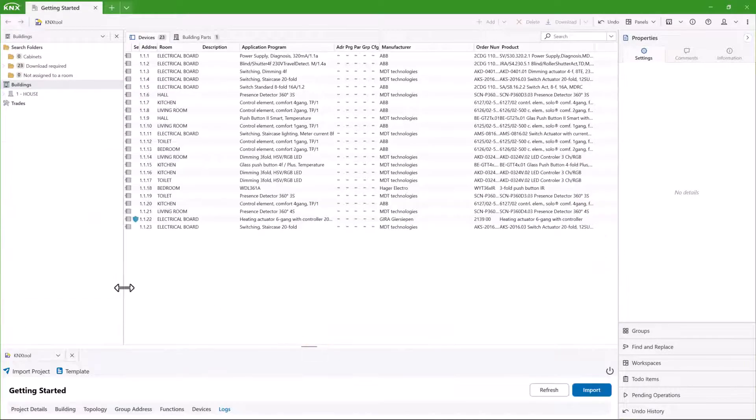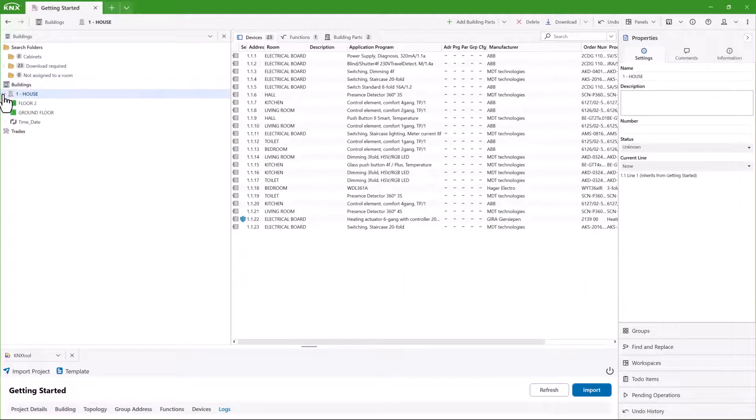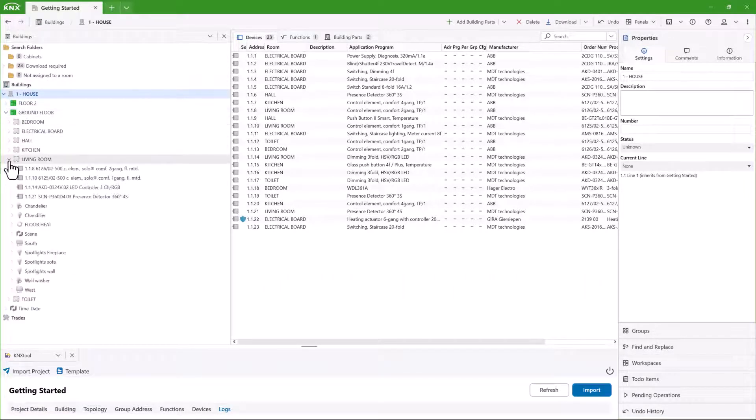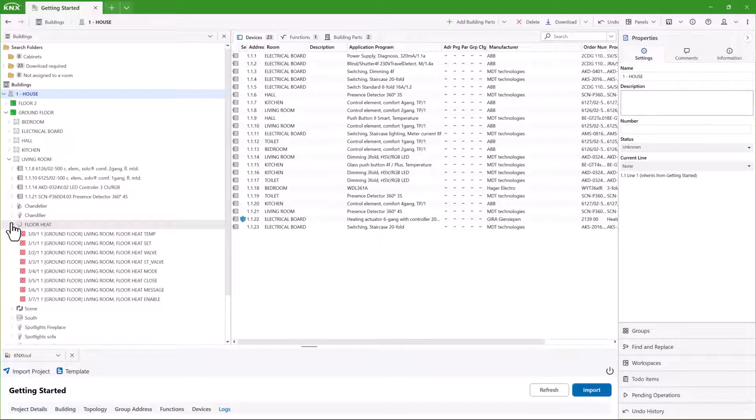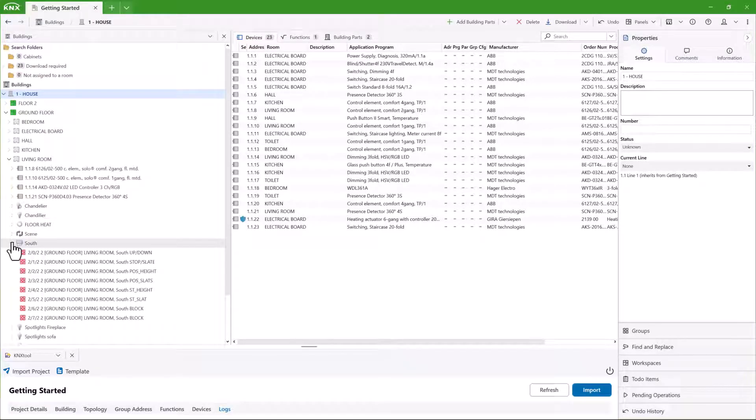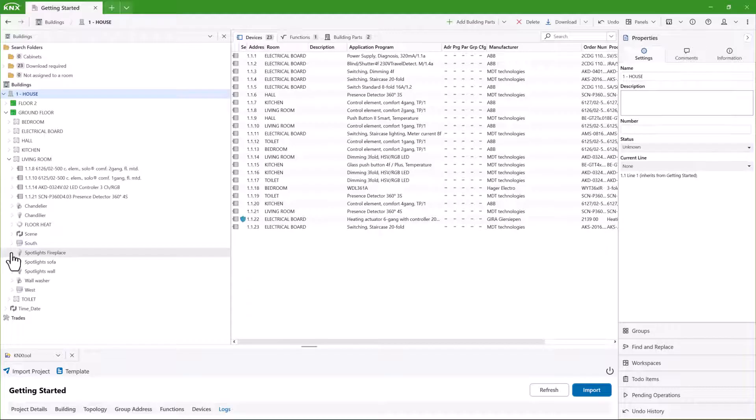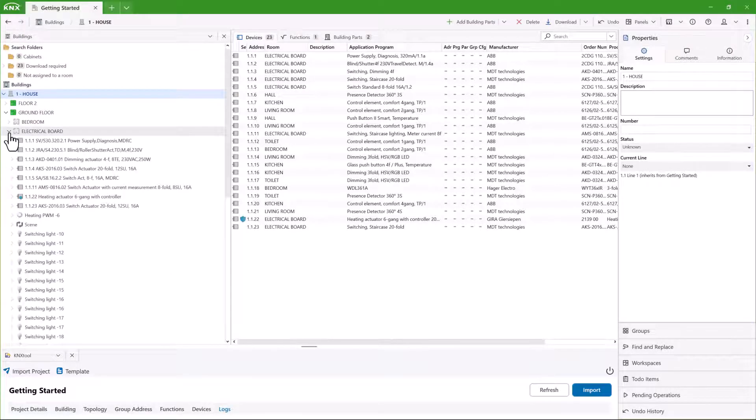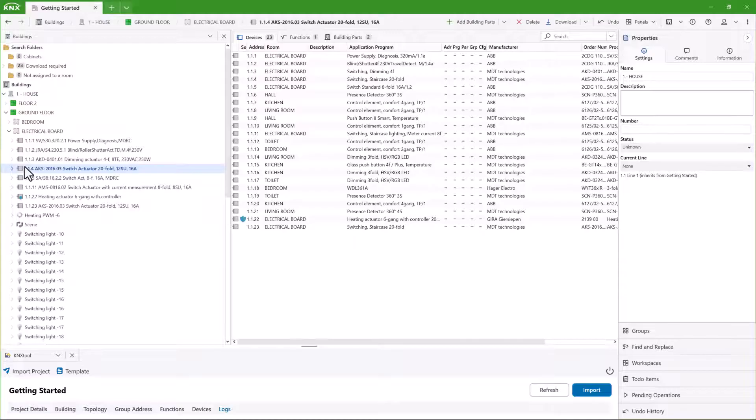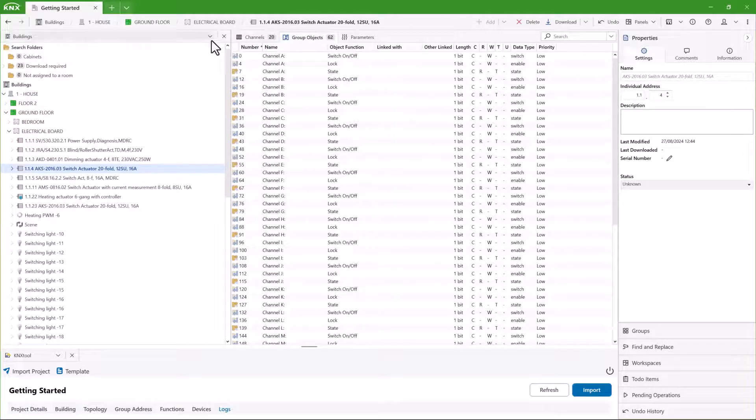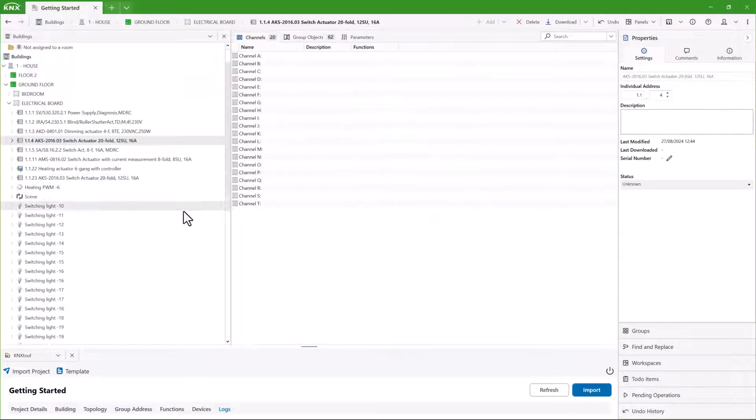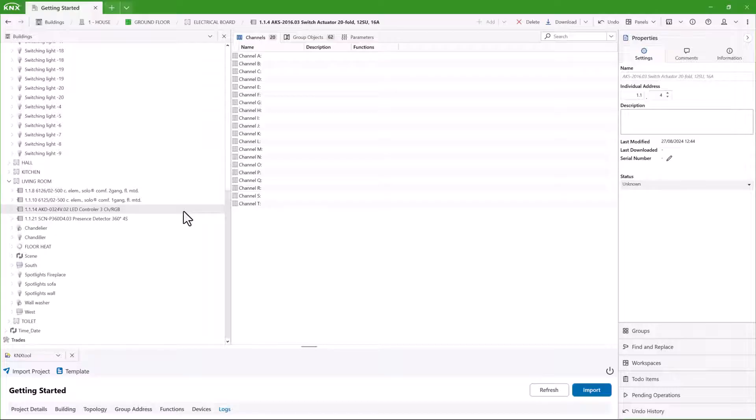Now the project is imported, you can see that the entire building structure has been imported with the group addresses and devices and more. By using the group address structure from the KNX tool, you automatically create ETS functions. With ETS functions, you can link multiple group addresses at once to a channel. You also get a better overview of the functionalities you have in a room.